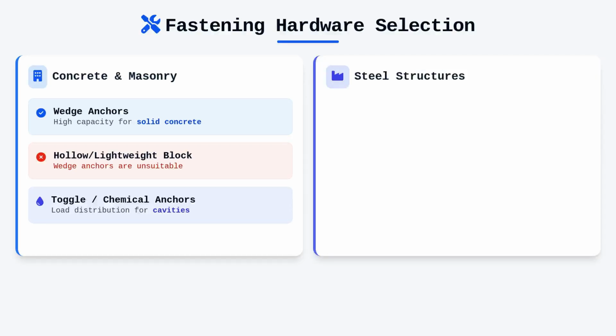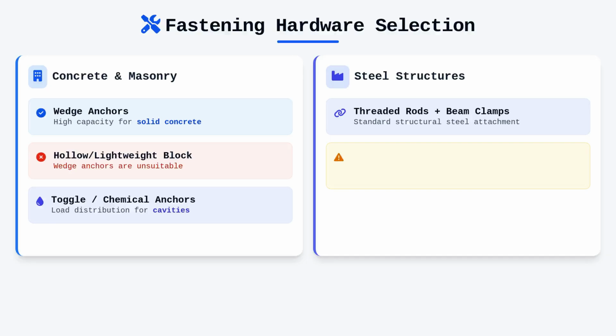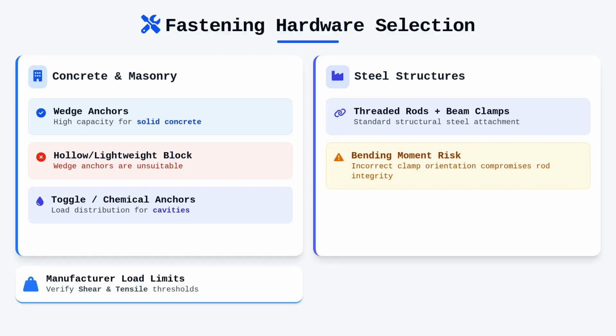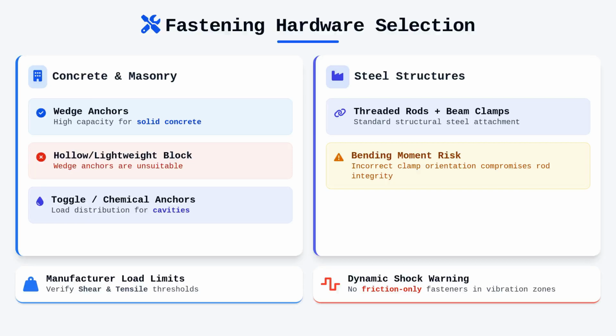For steel structures, threaded rods combined with beam clamps are common, but we must ensure that the orientation of the clamp does not introduce a bending moment that could compromise the rod's structural integrity. Each fastener has a manufacturer-verified shear and tensile limit, and the designer must ensure that the total load experienced by any single point of attachment never exceeds these thresholds. Never rely on friction-based fasteners alone if there is any chance of significant vibration or dynamic shock, as these can loosen over time and lead to a catastrophic failure of the entire pathway assembly.